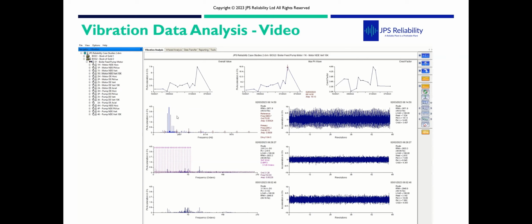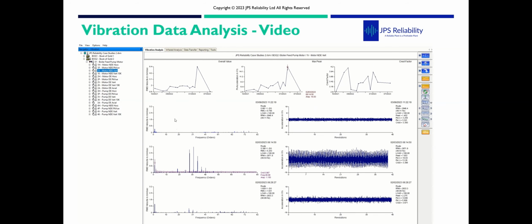What's good about this software is, obviously, the first thing you've got to do is make sure you've got your one order correct, because without your correct running speed, all your bearing defects will not be correct. So we go through the software, we toggle, and then we find the first peak, which we know is around one order, 48 hertz. We can toggle straight into RPM, 2,932 RPM. Make sure you get the correct RPM set across the whole asset.